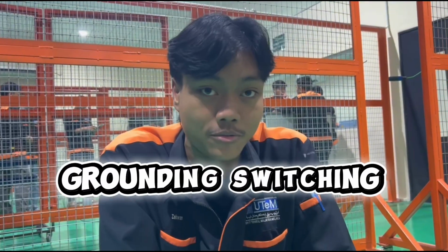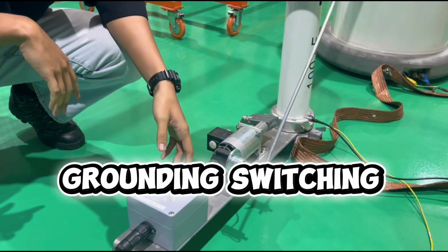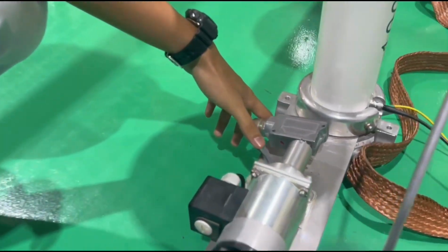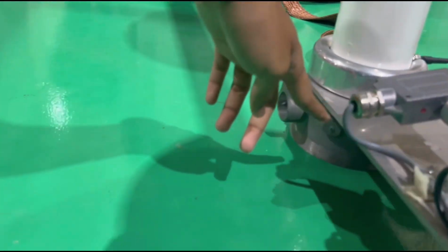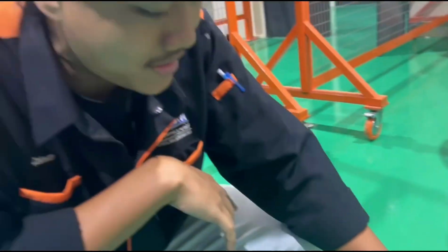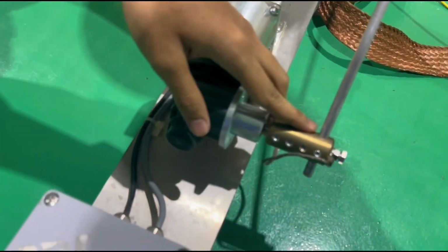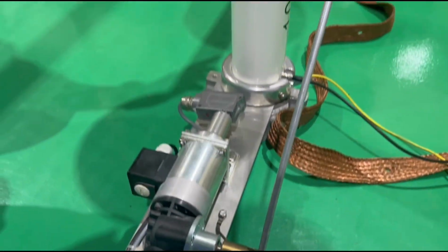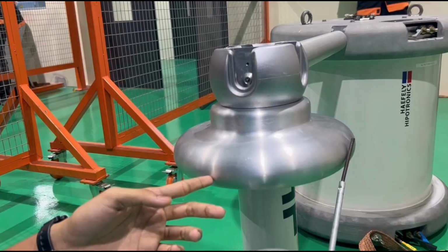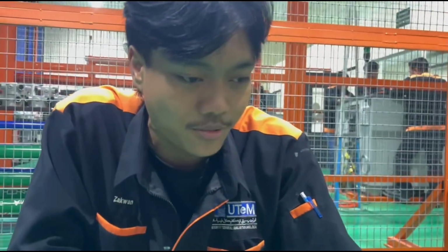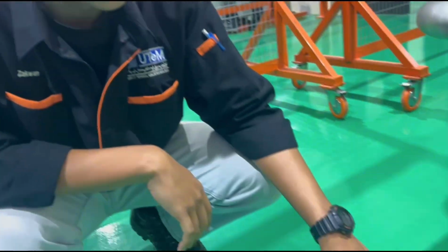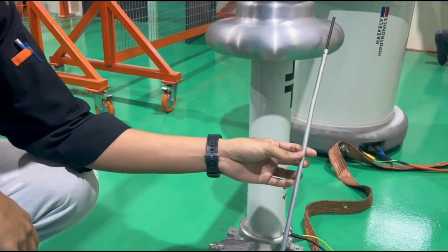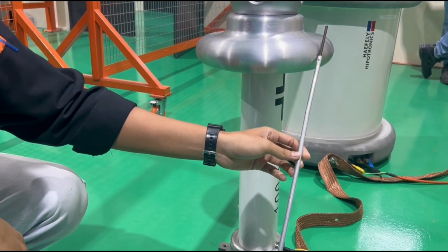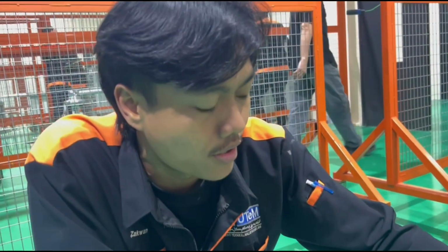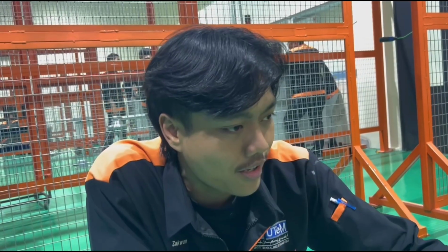I will explain about the grounding switch. This grounding switch connects between the measuring capacitor and the floor pedestal. As we can see here, this grounding switch has a testing rod, which connects with the electrode. The function of this grounding switch is to ground the high voltage construction kit, and this rod connects with the electrode to reduce corona discharge on the high voltage part.